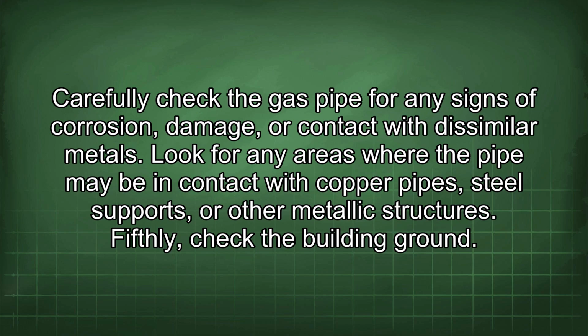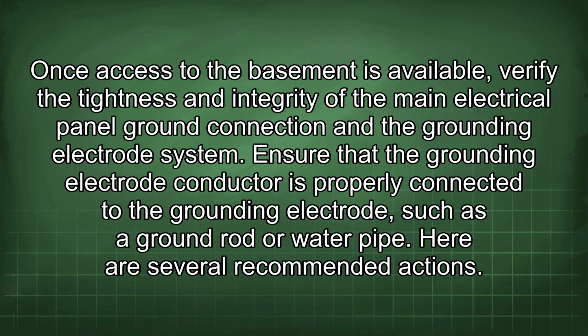Fifthly, check the building ground. Once access to the basement is available, verify the tightness and integrity of the main electrical panel ground connection and the grounding electrode system. Ensure that the grounding electrode conductor is properly connected to the grounding electrode, such as a ground rod or water pipe.